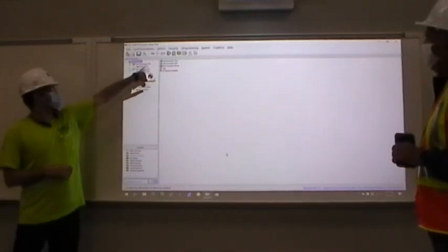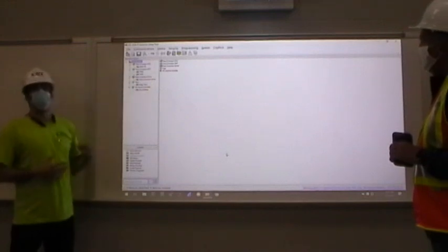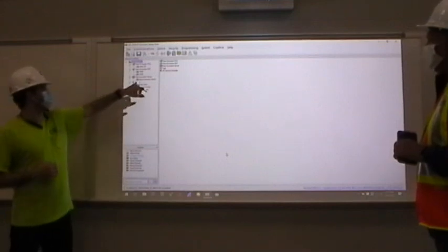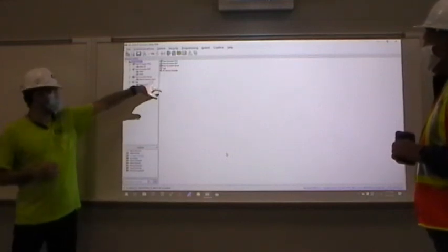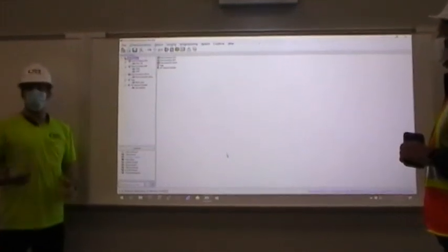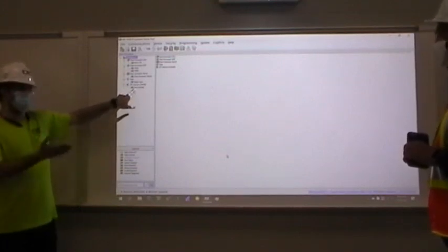Okay, here we go. You'll see class connection CPU, that is the main actual processor card. And you have class connection expansion cards. So these are ones, essentially all it's doing is just expanding the CPU to get the stations from all of the other areas. Class connection server is what is actually controlling the bell schedule and all of the messages that can be sent out. You have your Bogen input, like we said, is what's sending and receiving from the other building. VoIP interface is to connect to the phones.